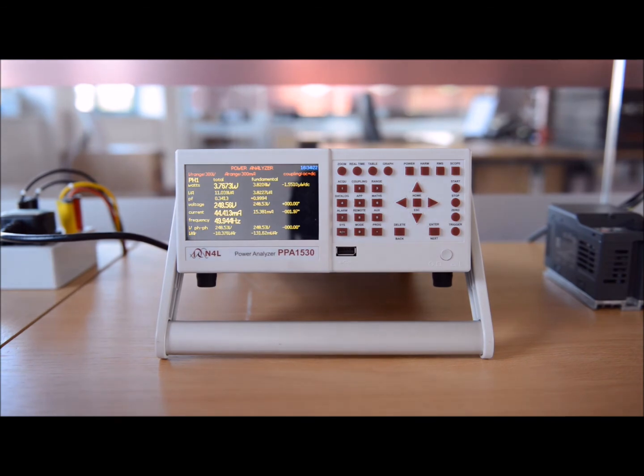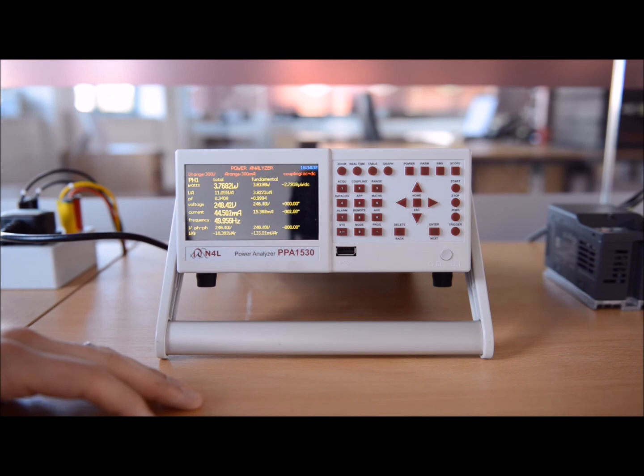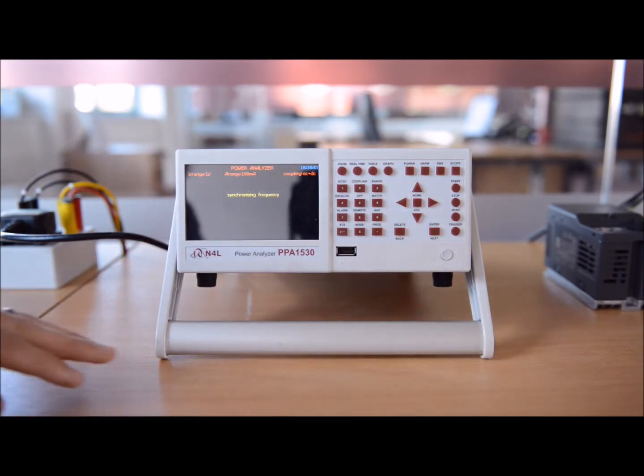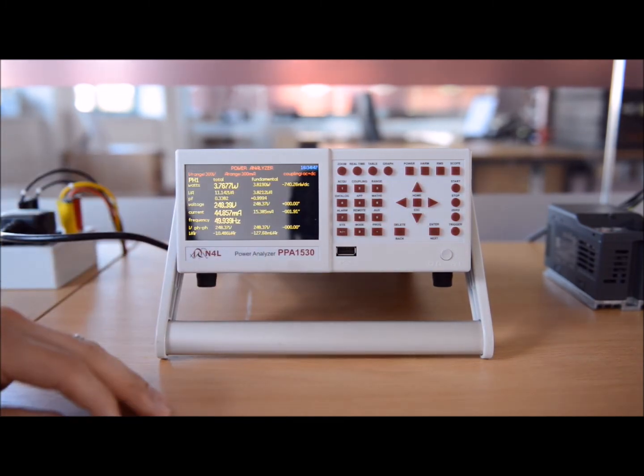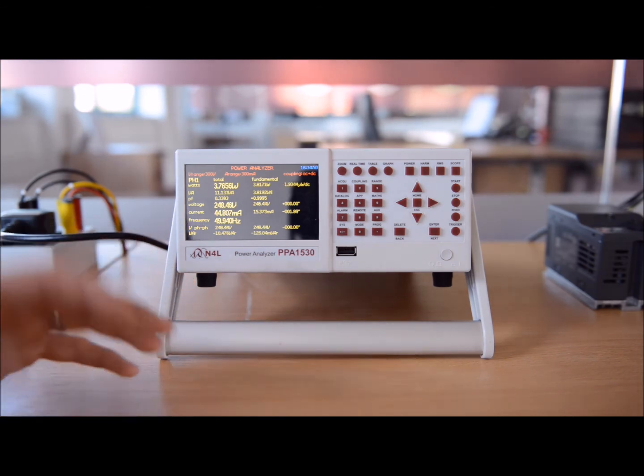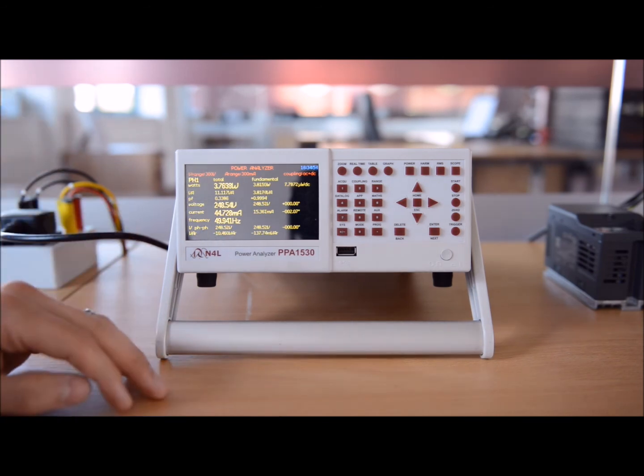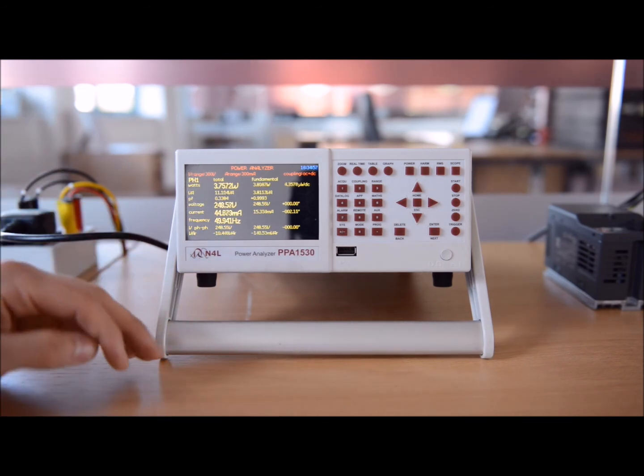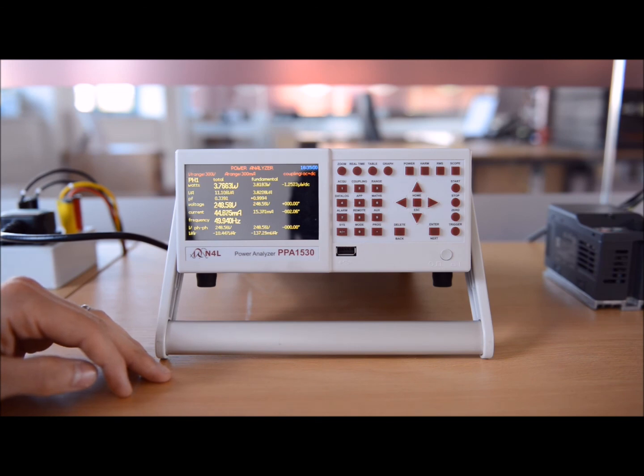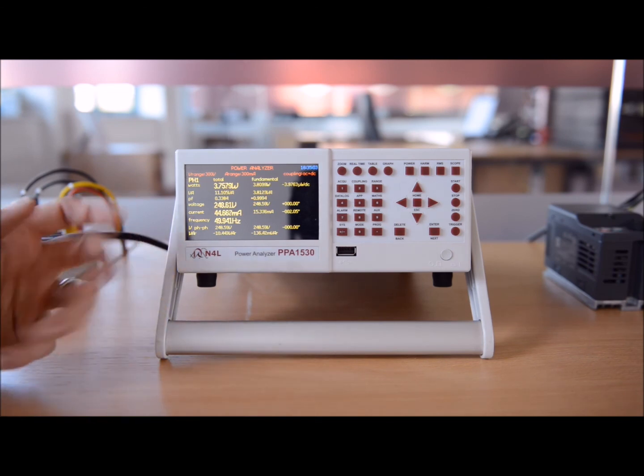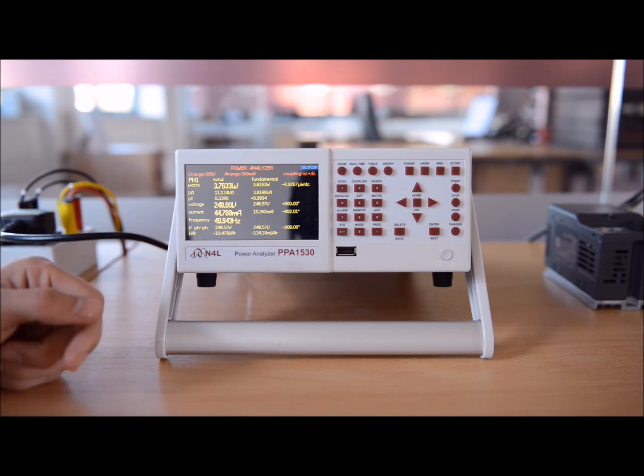Now, let's just discuss why we've chosen the 1500 for this measurement. One of the main reasons is that for the AC input measurement, providing that 0.1% nominal accuracy is okay for your application, then the input side is actually a simpler signal to measure. Although there are challenges, as we discussed, with peaky wide bandwidth current waveforms, it's not as complicated as the output signal, and at times when the very high accuracy instruments are not required, then the PPA1500 or even PPA500 would be adequate for the input side measurement, whether that's the DC bus or the AC input signal before the DC bus.